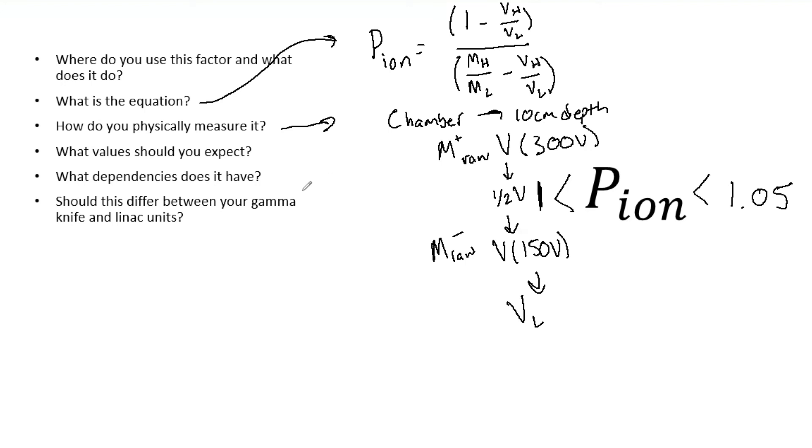So now what dependencies do we have? The first one is based on our equation here, obviously you see a lot of voltages. So our chamber bias is going to be our first dependency, and the bias is going to change the speed of ion collection.